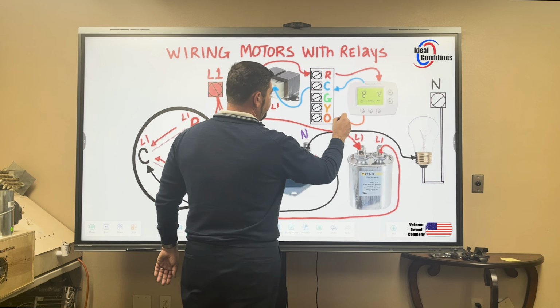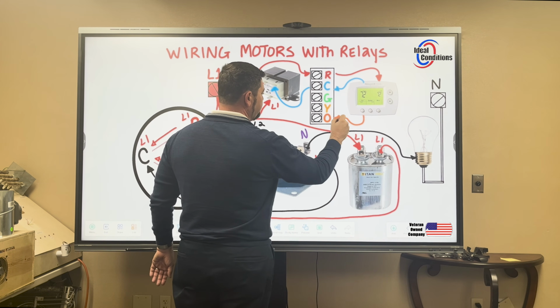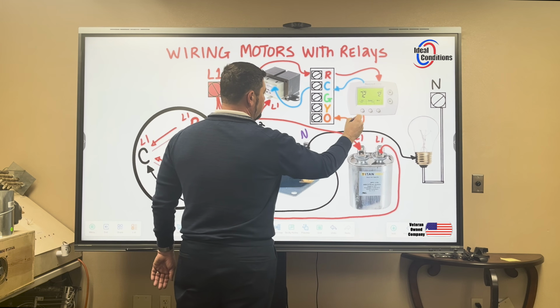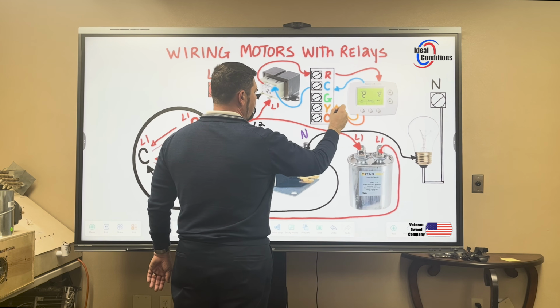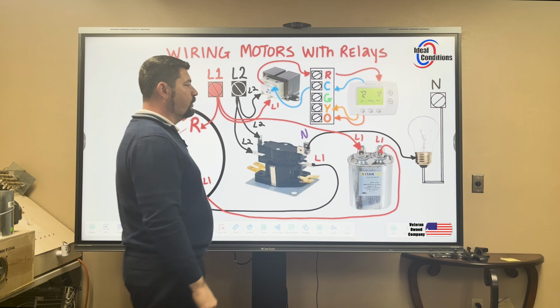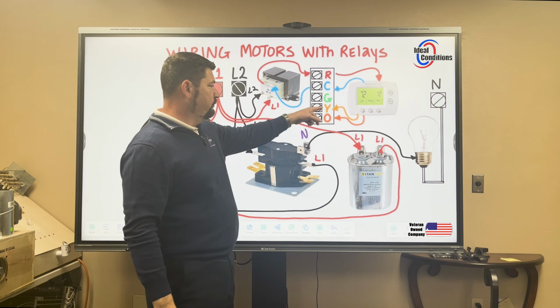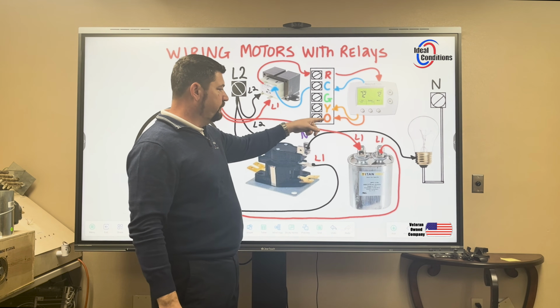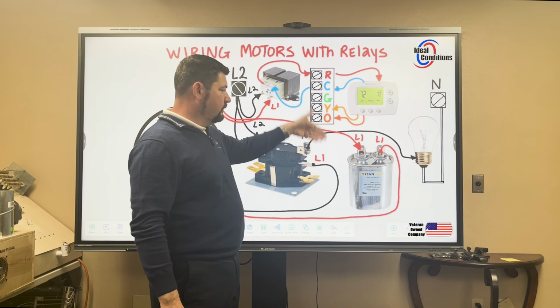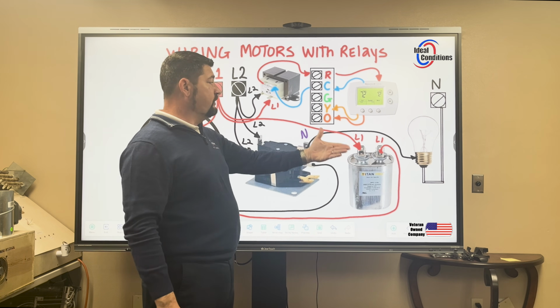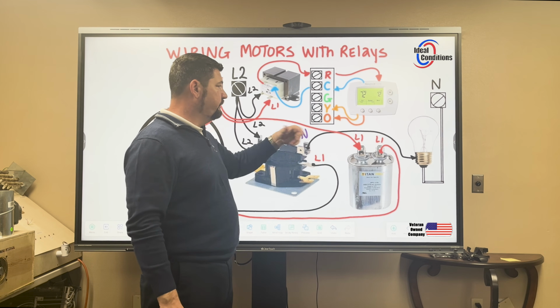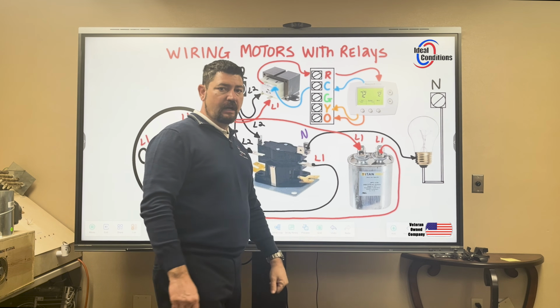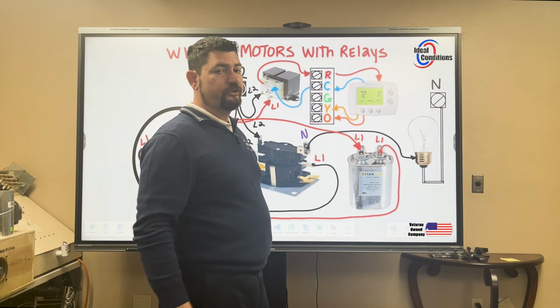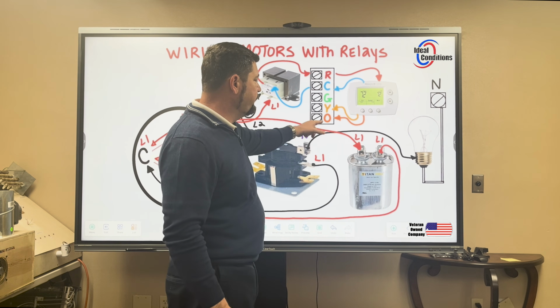we'll have 24 volts on O when we get a contact for cool. We'll have 24 volts on Y when we get a contact for heat, and a contact for Y on a heat pump with O will be in cool mode. If it's a straight cool air conditioner, then Y will not be contact voltage for heat. It's contact voltage only for cool. But as you see here, I have an O here.